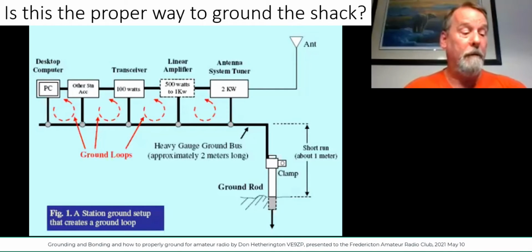Ground loops are formed when the individual ground wires of each equipment are connected to the main ground bus at a point that is distant from each other, such as this example. The individual station equipment already have their own ground reference, but when they're interconnected, grounding each equipment to the main ground bus as shown in this figure creates ground loops.